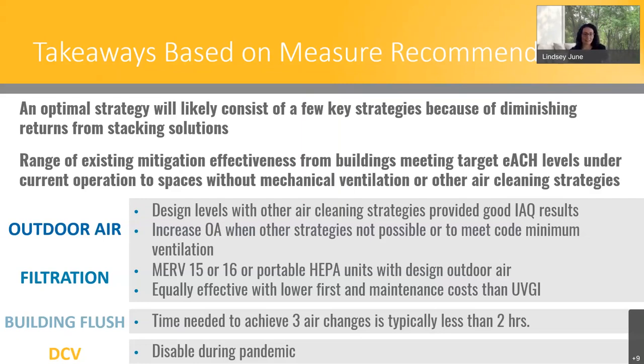On the building flush side, it's important to calculate the time needed for a 95% viral removal for a building flush and factor in your outdoor air levels and your filtration levels and your air cleaning treatment in order to minimize the flush time needed. And for demand control ventilation, it was found to keep that disabled during any epidemic situation. Next slide.